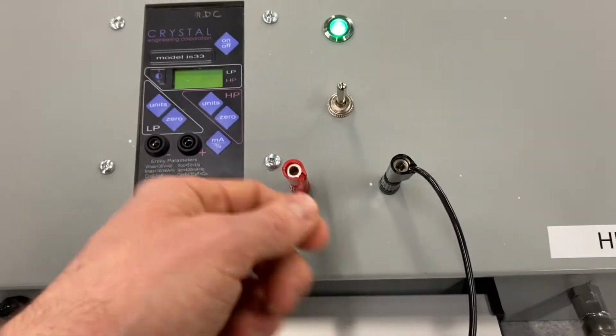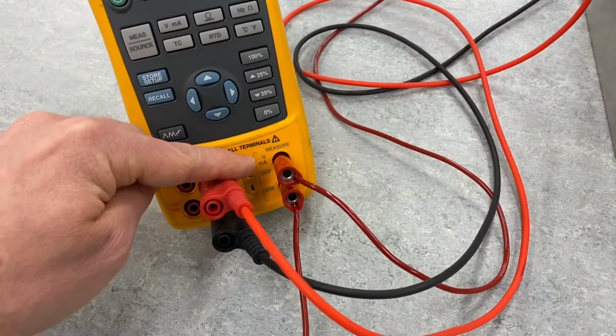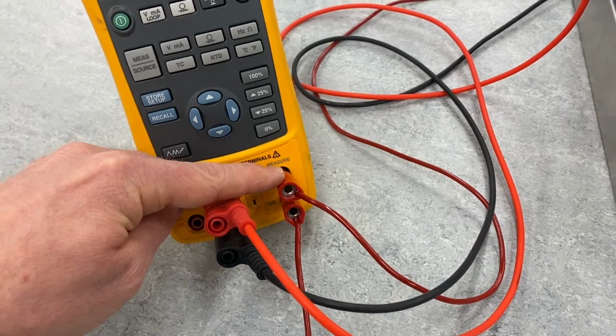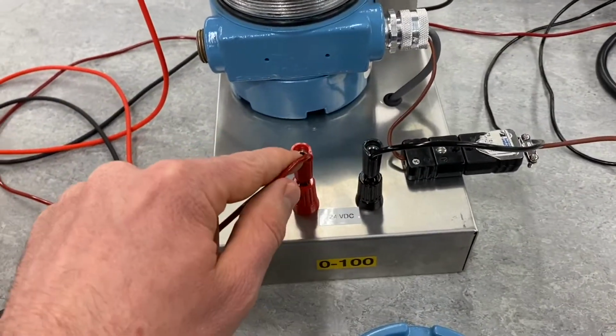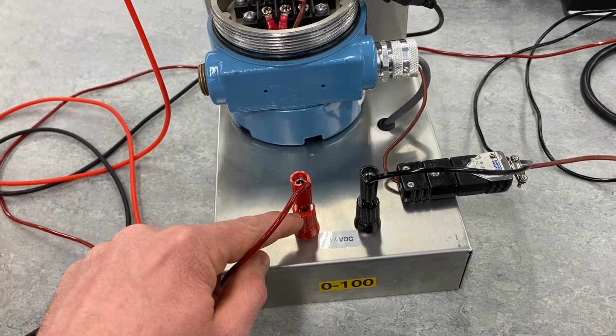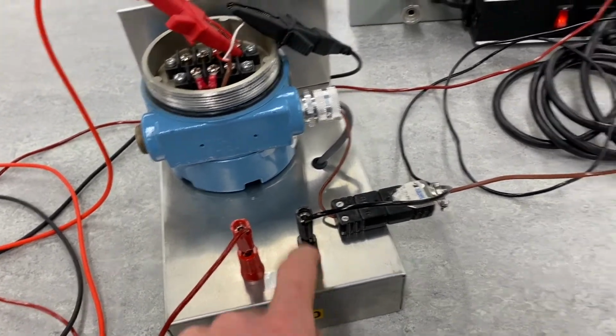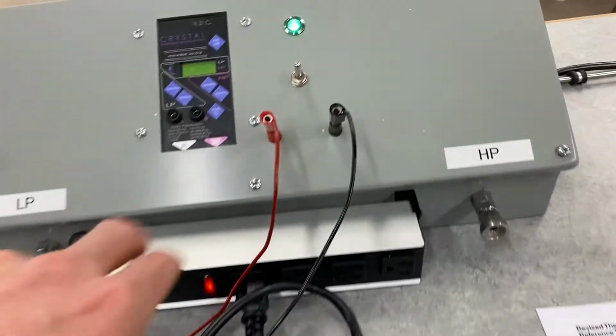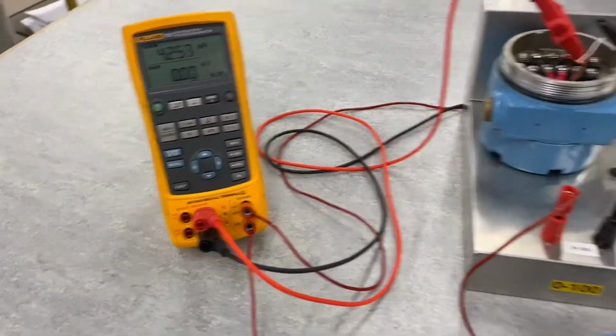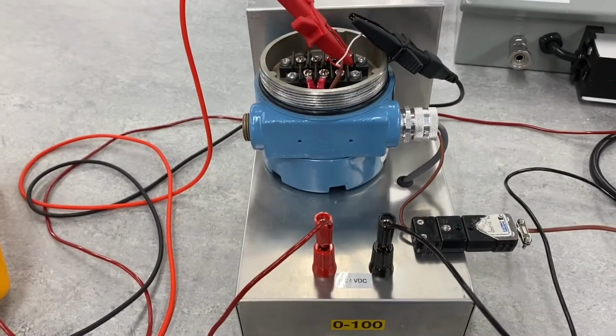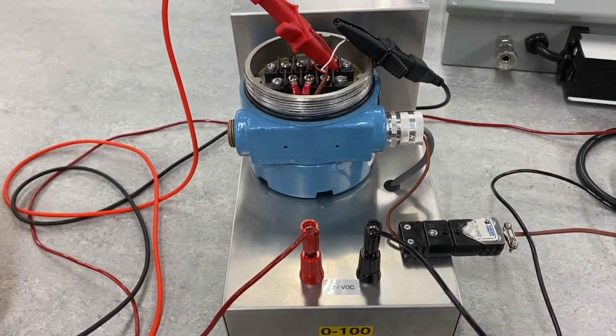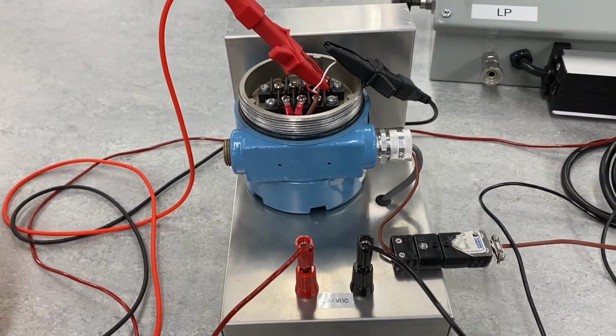The loop here is completed as follows: we start over here at our 24 volt power source. This lead goes over to the milliamp input on our meter, out of the milliamp input of our meter, and into the positive lead on our transmitter. Then from the negative lead of our transmitter, it goes back over to the negative lead of our power supply. So we have this meter hooked in series with the 24 volts and the milliamp output of our transmitter. So it's all connected up.